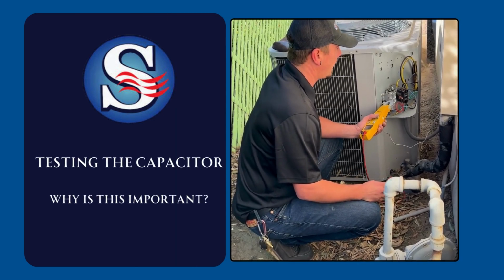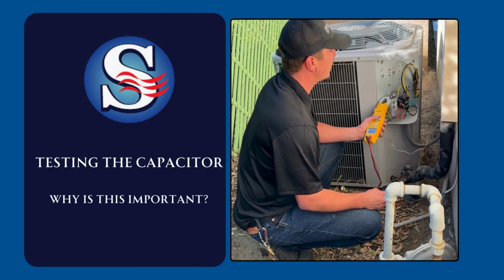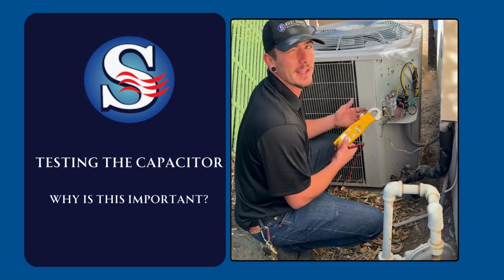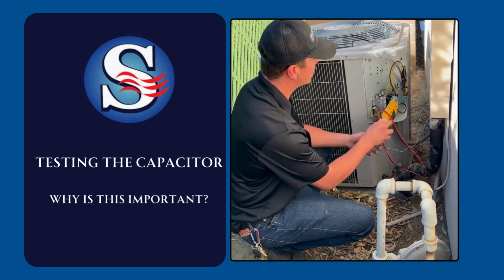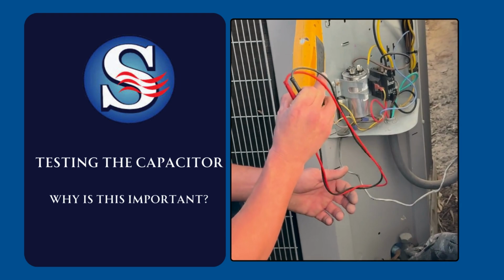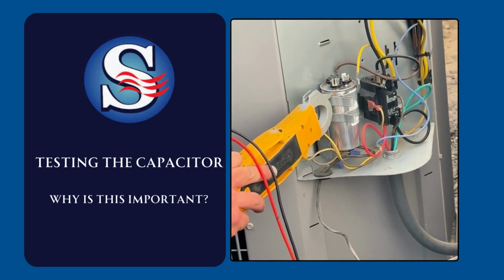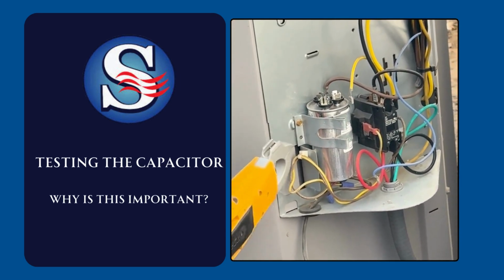So we're going to test the capacitor. This is one of the main start components. As you can see, this unit only has a couple start components. It's got a contact relay to engage the compressor and the fan motor, and this is the start capacitor to help the compressor and the fan start.